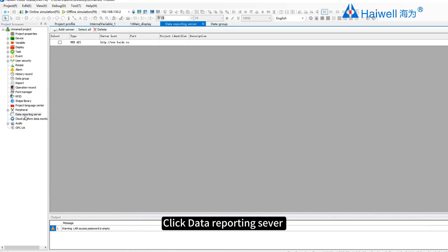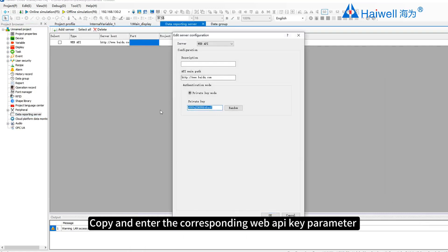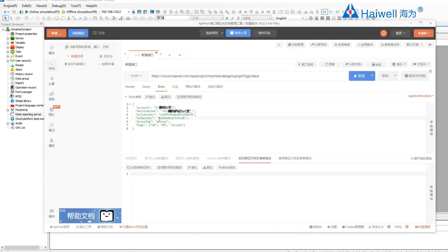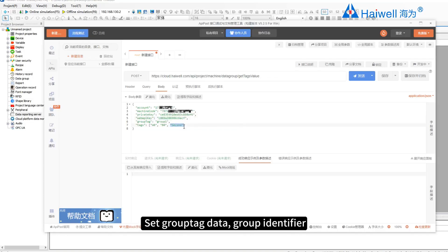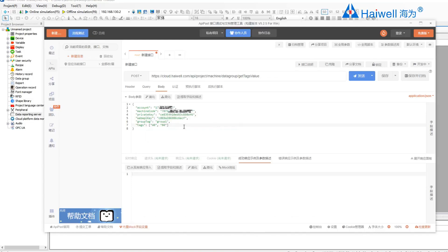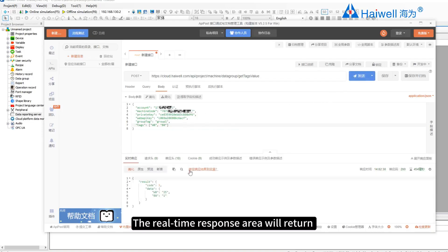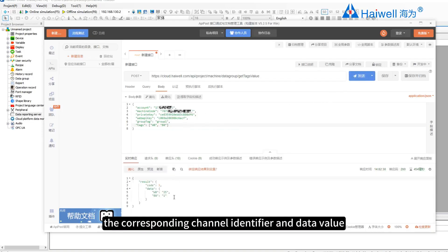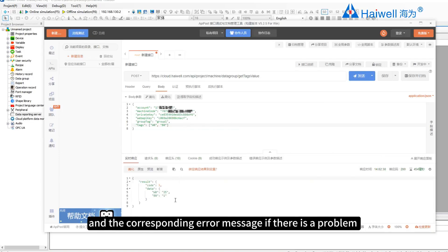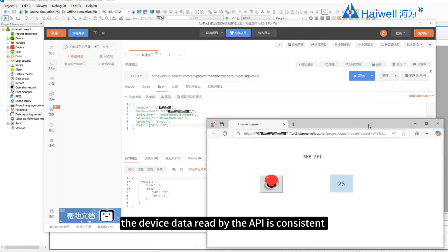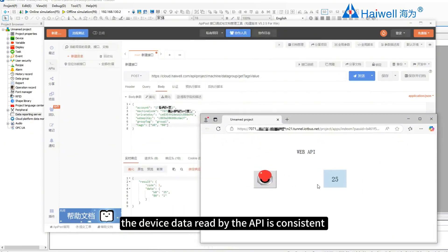Also fill in the parameters for the Web API key — we can copy it in SCADA. Click Data Reporting Server, copy and enter the corresponding Web API key parameters. Set the group tag (data group identifier) and tag (channel identifier) parameters. After filling in the parameters, click Send. The real-time response area will return the corresponding channel identifier and data value, and any error messages if there is a problem. The device data read by the API is consistent with the device — the read is successful.